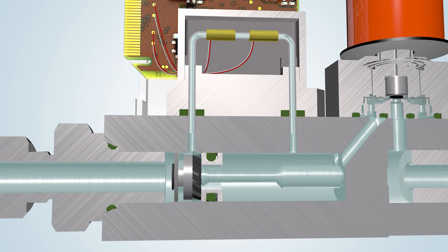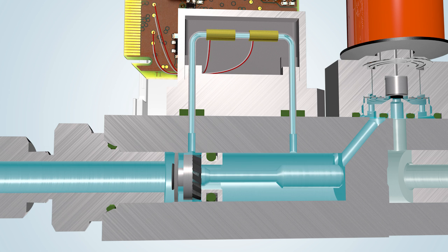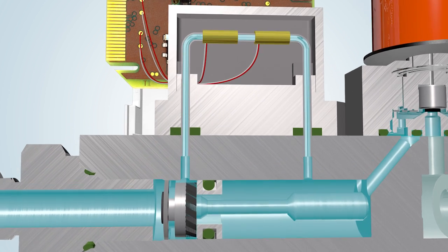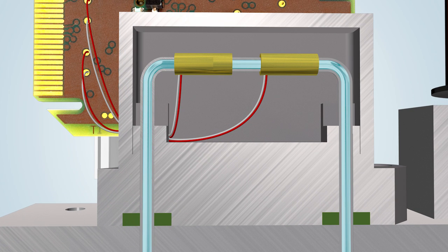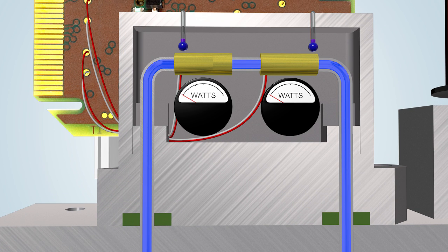The measuring part of the instrument consists of a patented laminar flow element combined with the thermal mass flow sensor. Once the instrument has been connected to the process line, the pre-pressure can be set. The body and the sensor are now filled with gas. The sensor consists of a thin capillary tube fitted with two combined windings for heating and temperature measurement, and an additional temperature sensor ensuring superb sensor stability.